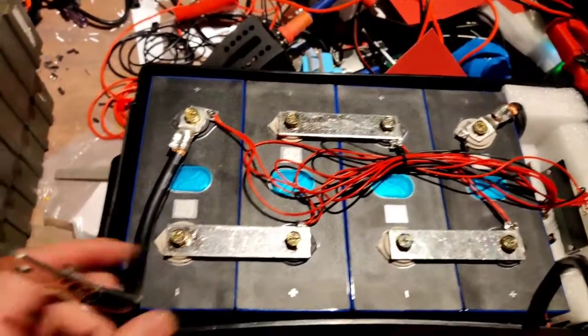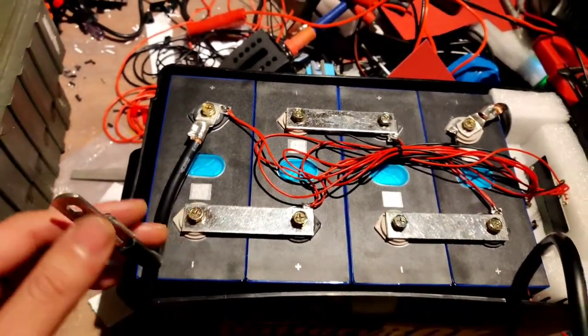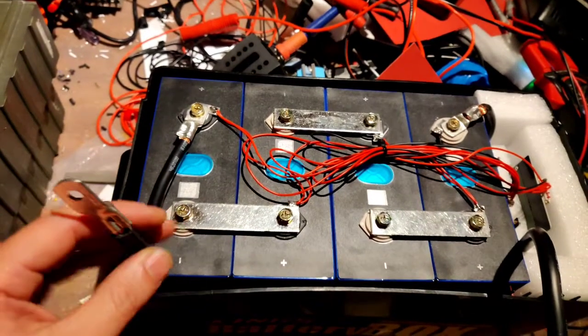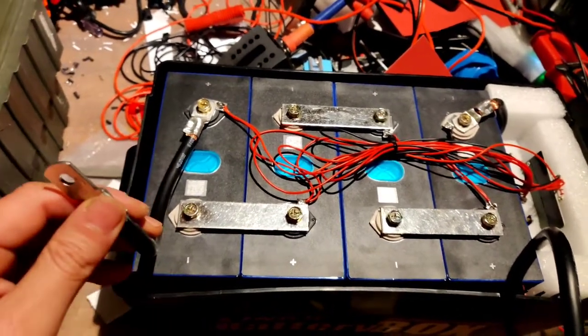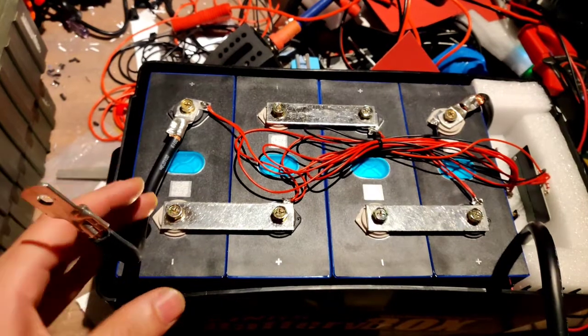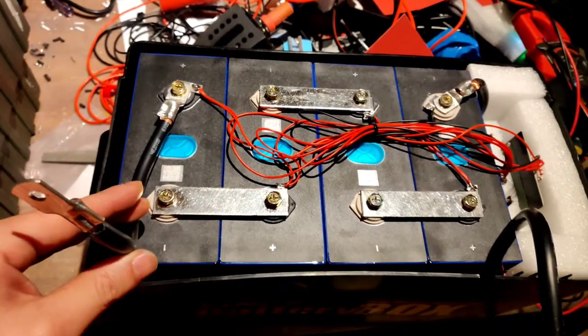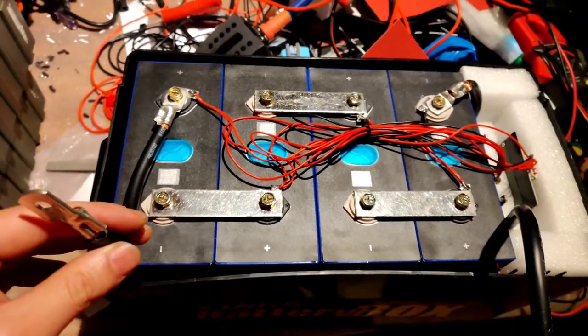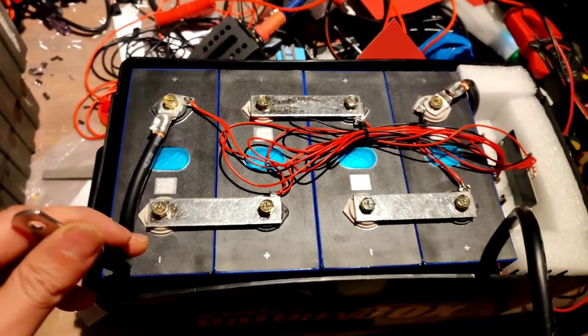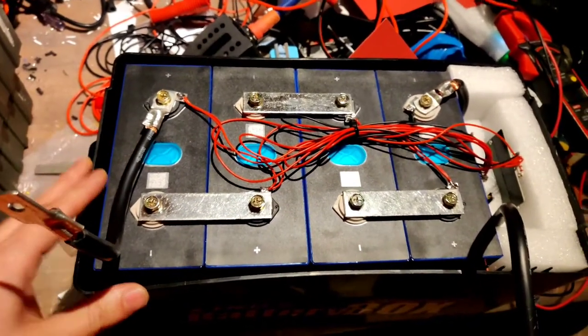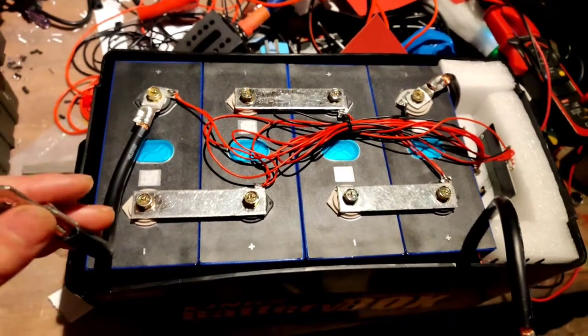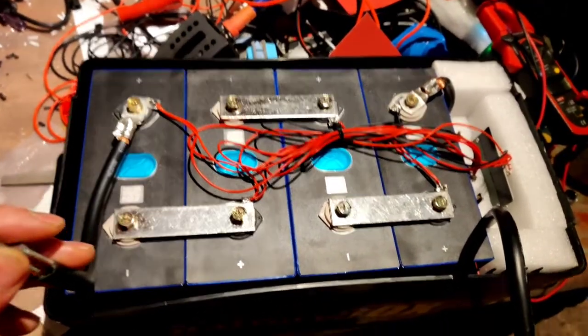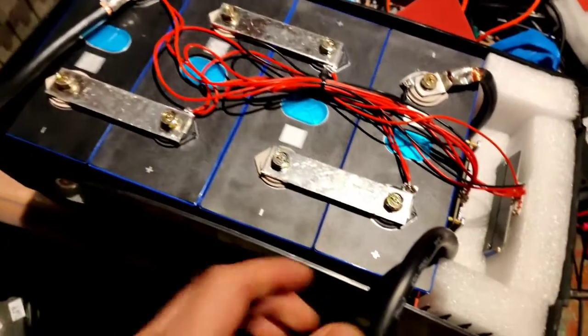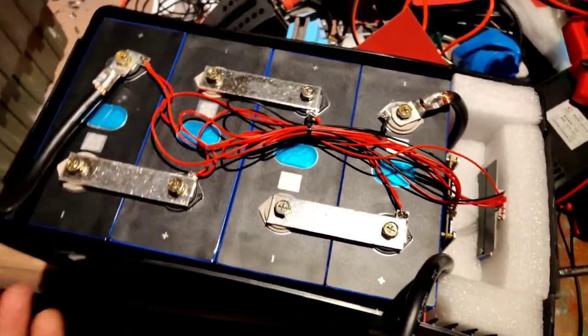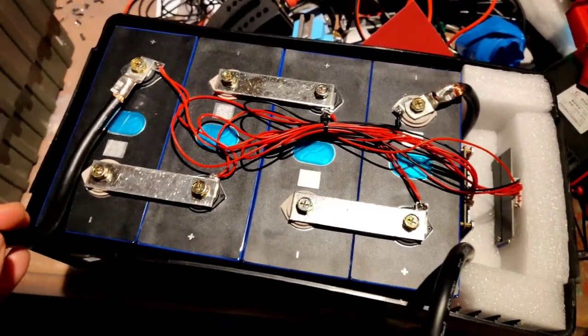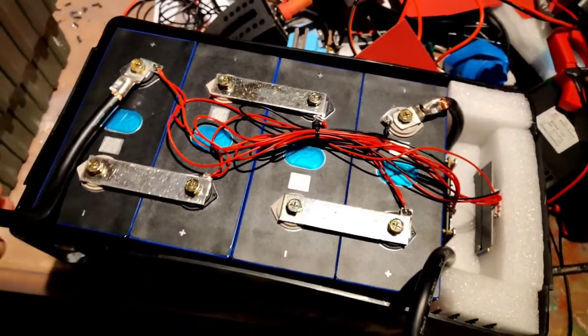And what I've done is I've used 35 squared cable, quite heavy duty in fact, because I'm going to be running this off a 2.5 kilowatt, 2500 watt inverter. So from 12 volt up to 240 at 2500 watts. So that's quite demanding. And if you're not using such a high powered inverter on your load side, you can go thinner for your output cable. So that's up to you.